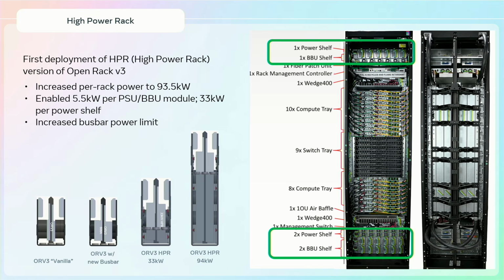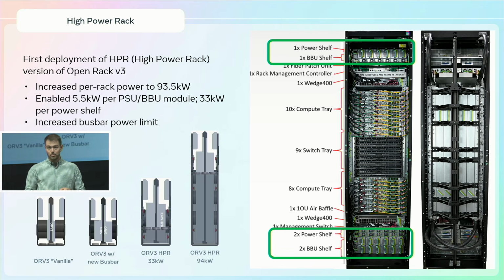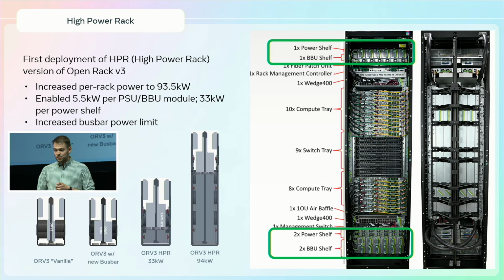Jumping to the rack itself, circled in green are those power components I talked about earlier. This is the first deployment of our high-powered rack version of OpenRack v3. Interestingly, OpenRack v3 was originally launched with more traditional storage and compute platforms in mind. As we've increased the power in a rack to support denser AI systems, you can see what this means in practice, like the thickness of copper on the bus bars, dramatically bigger than our lower power OpenRack v3 original on the left. We increased things with a 600 amp bus bar, and now we're all the way up to a 94 kilowatt bus bar in the back of the rack.